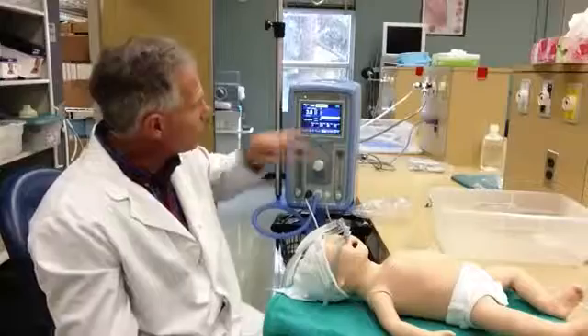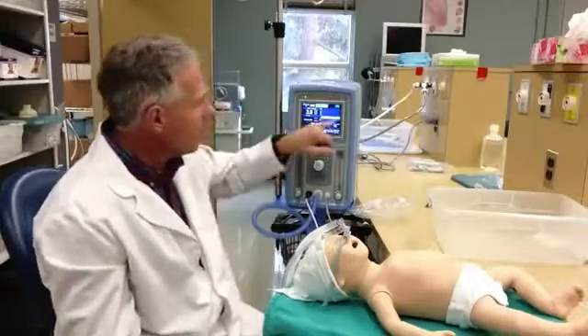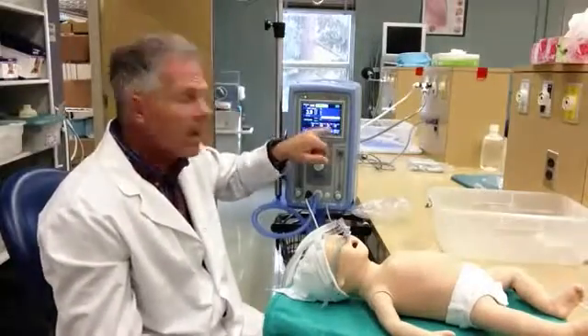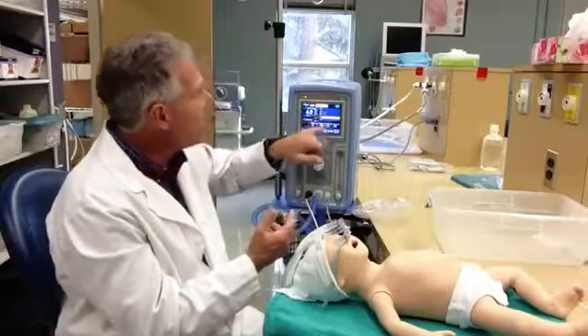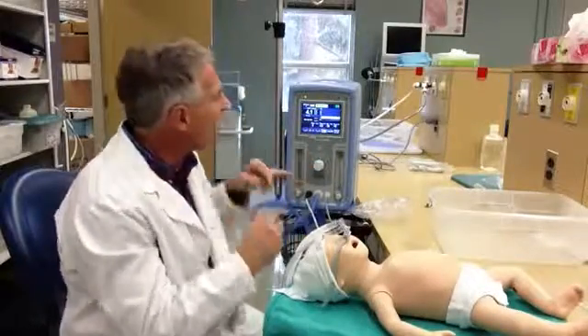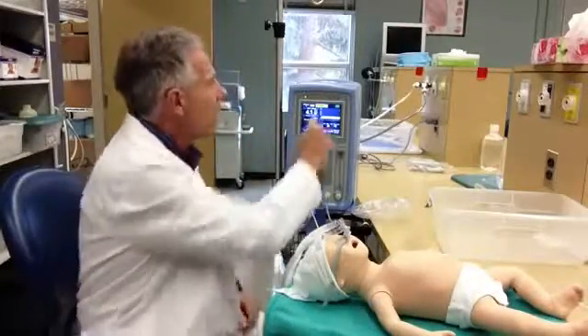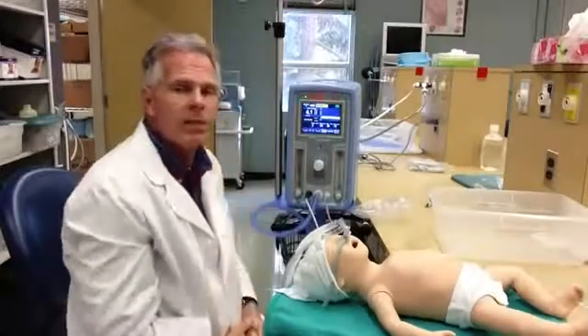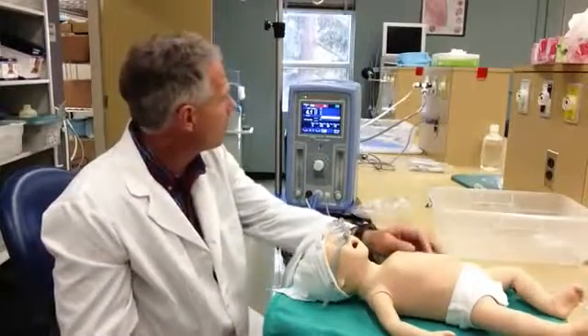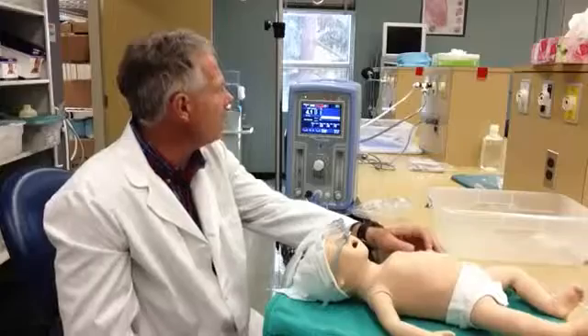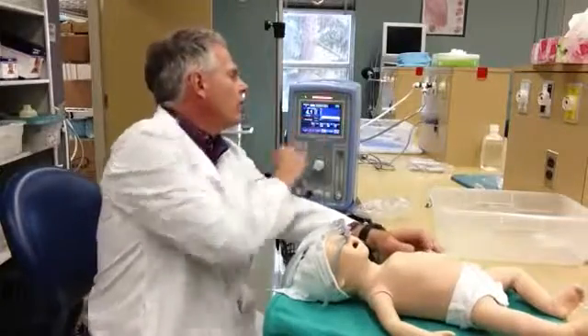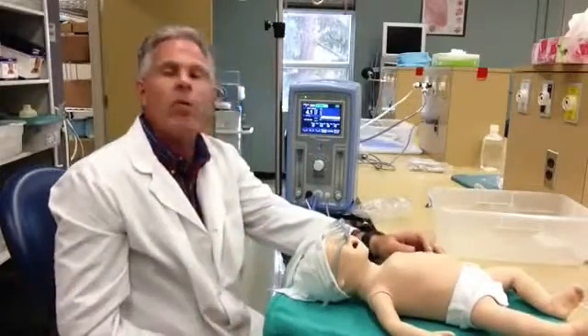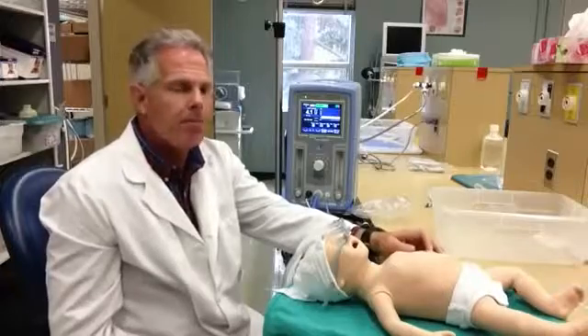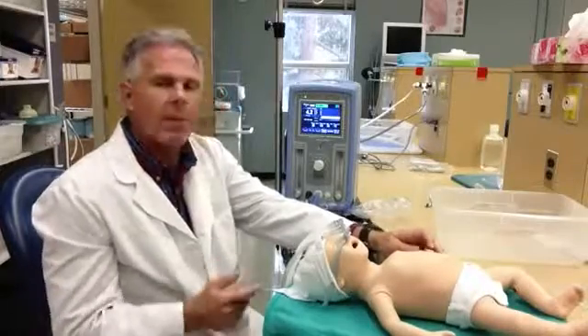You notice once our apneic period has gone through, so it's been more than 15 seconds, it kicks in, giving us the backup rate of 20 and gives us an alarm. You can silence the alarm just by tapping it. Now, if the patient starts breathing again, you're going to reset the alarms, and it'll be green, once the patient starts picking that up again.